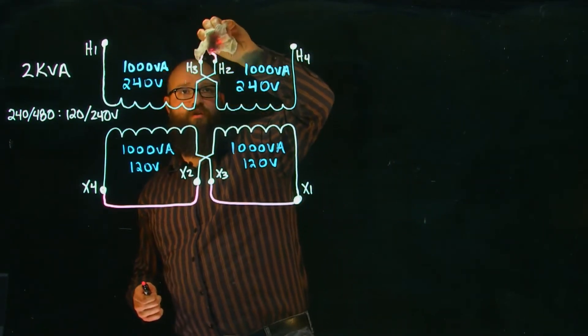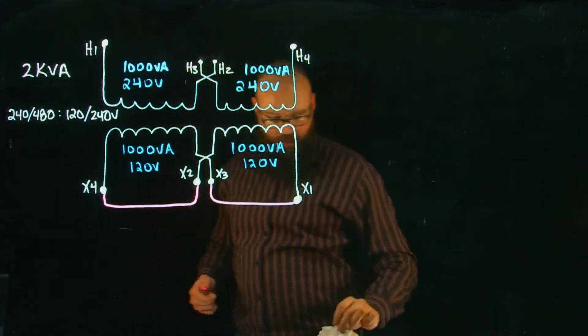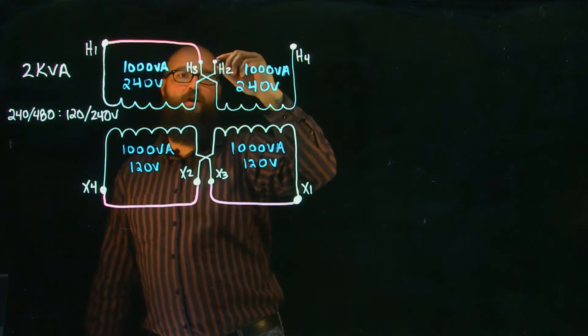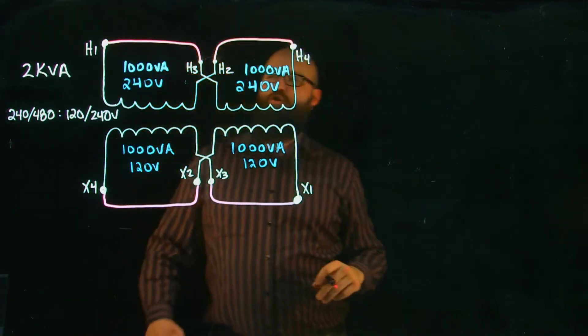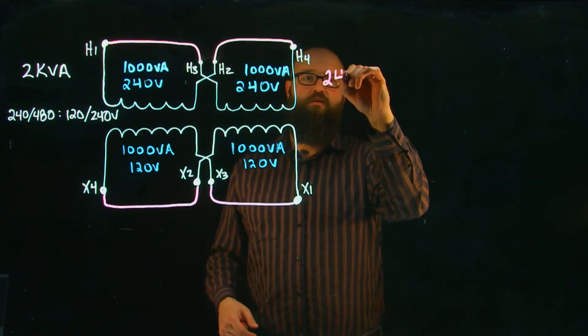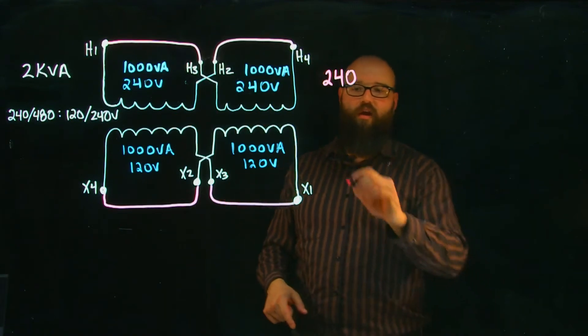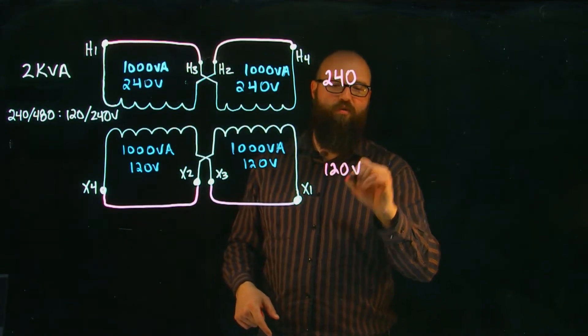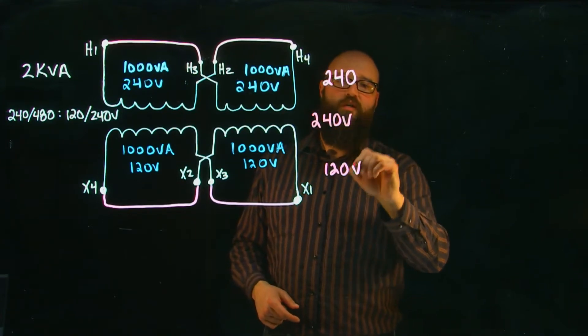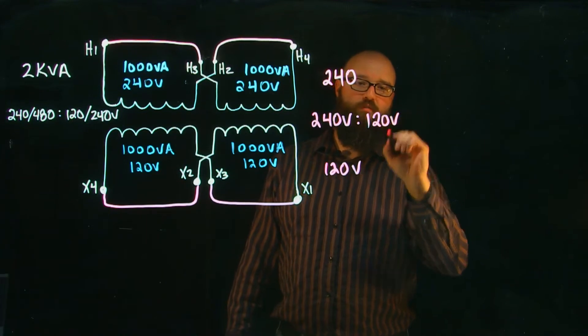This time we're going to remove the series connection on the primary and parallel it up. With two 240 volt coils in parallel I end up with 240 volts on the primary, and with the secondary still in parallel I end up with 120 volts on the secondary. That gives us a 240 volt step-down to 120 volt transformer.